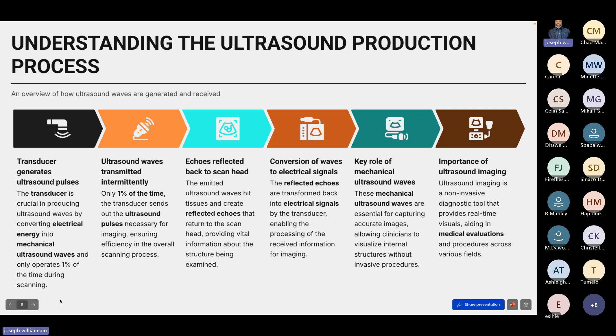So the conversion of waves to electrical signal is how we read it. Again, electrical signal excites the transducer, the transducer sends out a wave, it runs into something, bounces back to the transducer and tells it that there's something in my way, and here's a picture of the thing that I just bounced on. That, in a nutshell, is what you're reading when you're looking at the ultrasound image. The key role of the ultrasound wave is essential in capturing accurate images, which means that if you don't know how to manipulate that wave as it comes back, you're not going to be able to visualize those internal structures adequately. And ultrasound is one of these sciences, as I said before, where you can either create a disease or make it disappear based on the settings of your equipment.